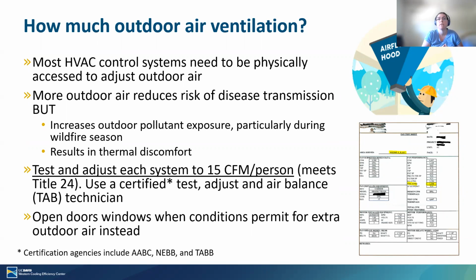So my recommendation here is to adjust HVAC systems to provide the design outdoor air rate, which in California is 15 CFM per person, and then use a certified test, adjust and air balance technician to do that testing and provide that documentation. So I just put an example here. This is an example test report from a TAB technician. This particular one was certified. There are 3 agencies here that I recommend that have the credentials essentially to do these tests. And they go through and measure, for every single room, the outside airflow rate for that room.